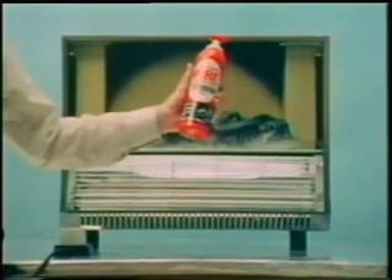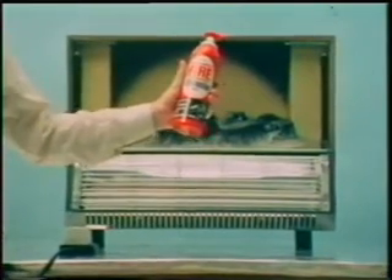Another demonstration, and we'll need the correct type of fire extinguisher handy for this one. The greater the current to be carried, the thicker the cable must be. This 2,000-watt electric fire takes a high current. Let's look at what happens if we connect it to the mains with thin lighting flex, which isn't intended to carry such a big current. The wire inside the insulation is thin, and its resistance will cause it to heat up as the current flows. After a quite short time, the two 1,000-watt heating elements are taking a big current — too big for this flex.